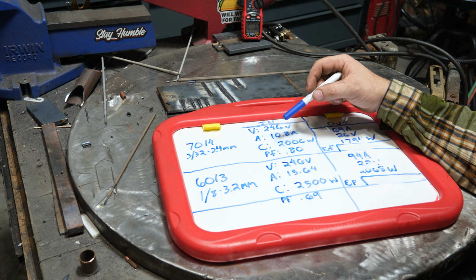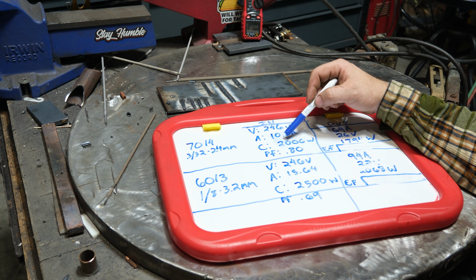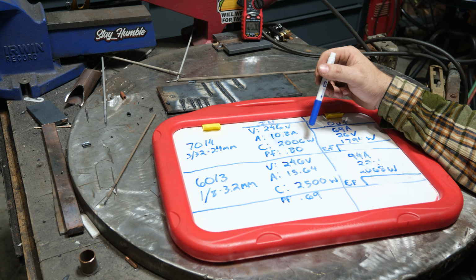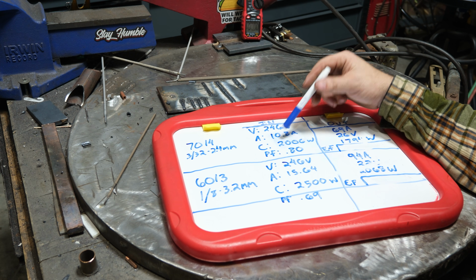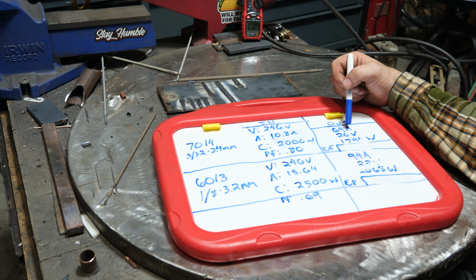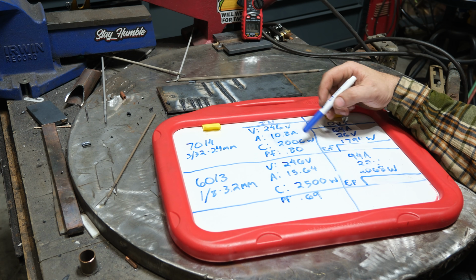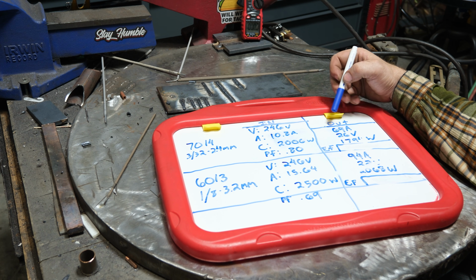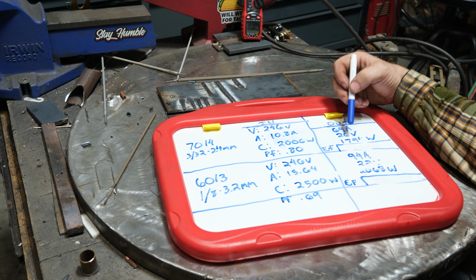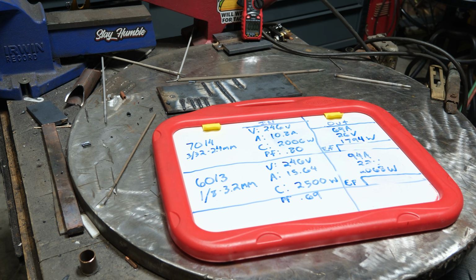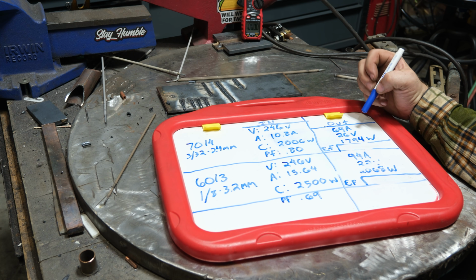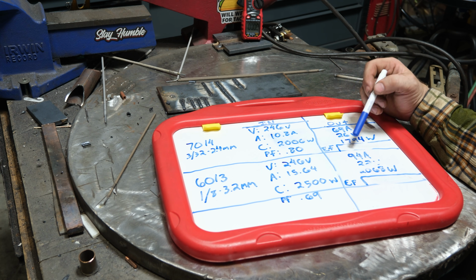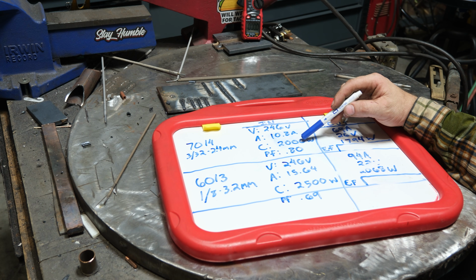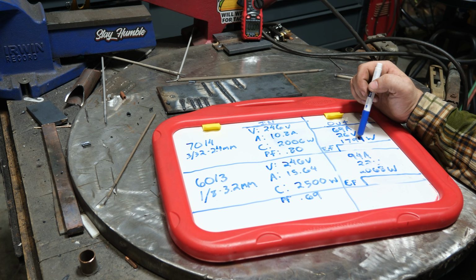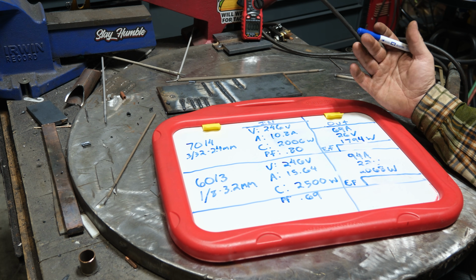The C stands for consumption. This device actually consumed 2006 watts, which isn't really that bad, all things considered. Power factor was 0.80, and this is at a 70 amp output. These are all the factors on the input side. The output of the welder, we saw 69, 70 amps, 26 volts while welding, which is a total of 1,794 watts. So we can calculate its efficiency if we know what it's actually consuming, corrected for its power factor, along with the wattage that it's outputting.